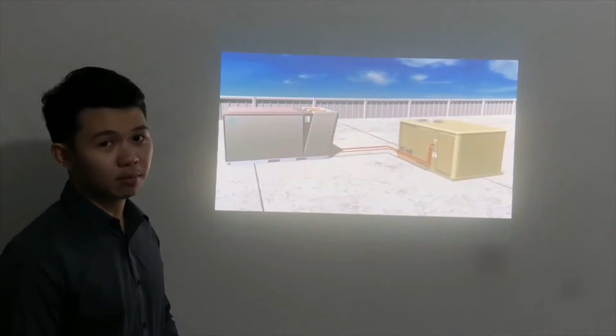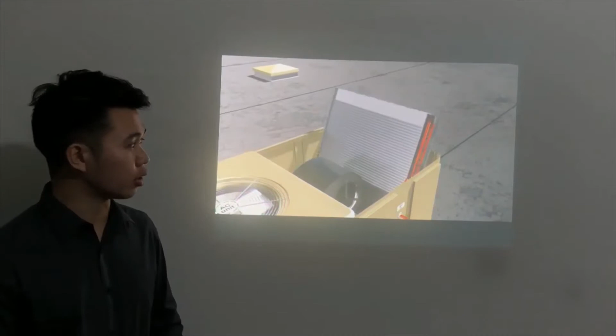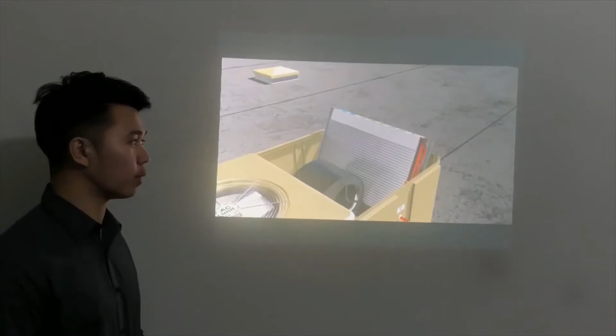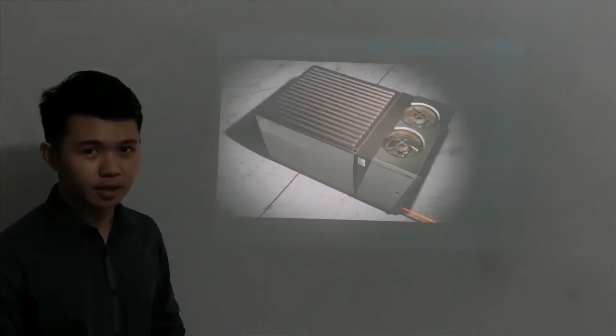Now, the operation is automatic and simple. The energy storage system stores energy at night and delivers the stored energy during the peak of the day. The ice energy storage integrates with the existing air conditioner by adding a new ice evaporator coil to the unit. The ice energy storage system operates in two basic modes: ice cooling and ice charging.